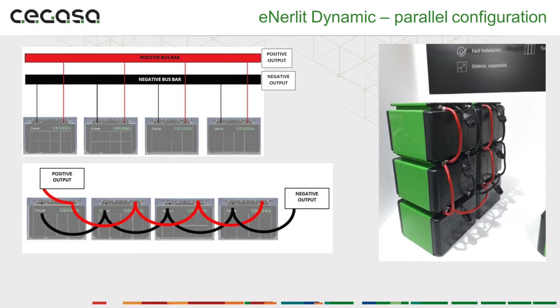What is recommended, depending on the systems we are working with, is that we need to find the balance. With lithium batteries, probably the biggest challenge is balancing the system, making sure the cells and the different batteries are equalized. Especially in stationary systems, we recommend the use of a busbar, connecting each battery independently to it. This way we ensure the balancing of the system.